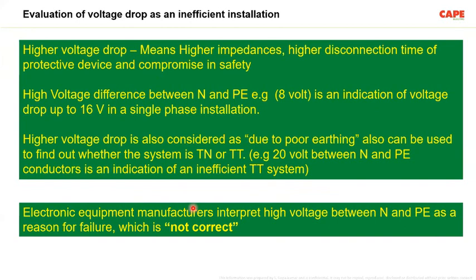Electronic equipment manufacturers such as UPS and lift vendors say that a higher voltage of neutral to earth, 10 volt or 8 volt between neutral and earth, is the reason for the failure of their equipment, which is actually not correct.